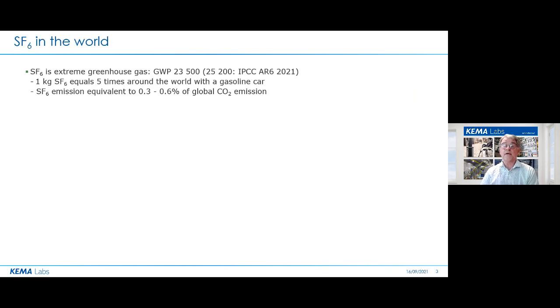So first, speaking again about SF6, as Antonio mentioned already, SF6 is the strongest greenhouse gas. The GWP of 23,500 is well known, but a few weeks ago it was revised by the IPCC to 25,200, so even more. This implies that 1 kilogram of SF6 roughly means circling the world 5 times with a gasoline car. The global impact of SF6 emission is estimated at several tenths of a percent of the global 40 billion ton of emission of CO2.